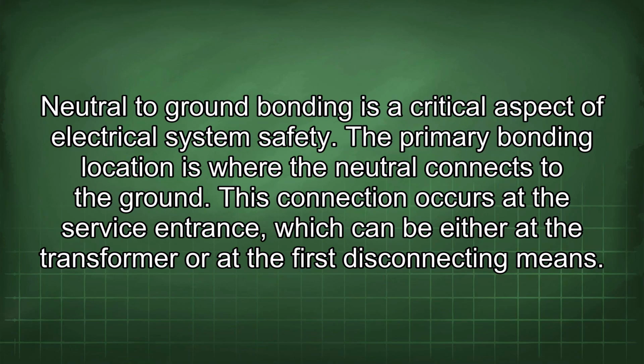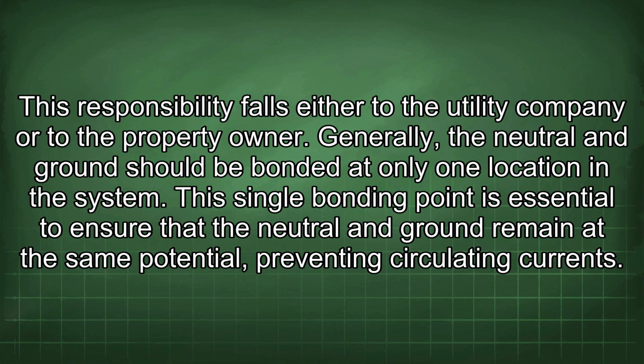Neutral to ground bonding is a critical aspect of electrical system safety. The primary bonding location is where the neutral connects to the ground. This connection occurs at the service entrance, which can be either at the transformer or at the first disconnecting means. This responsibility falls either to the utility company or to the property owner.